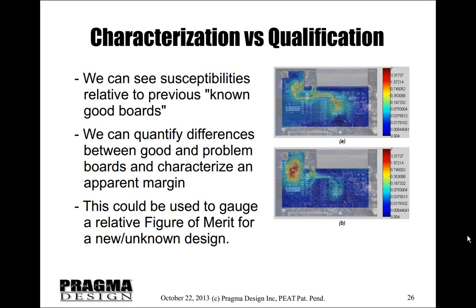And then I forgot the other question - how do you do the susceptibility test, and is it needed for a complete scan? The susceptibility test involves injecting the pulse into the probe as it's scanned across the board. Susceptibility scanning is the opposite of EMI scanning: with EMI scanning you're listening from the probe to the board, while with susceptibility scanning I'm injecting glitches through EMI into the board that I know what they look like. You don't need that if you have a hard failure, since you already know which chip blew up.